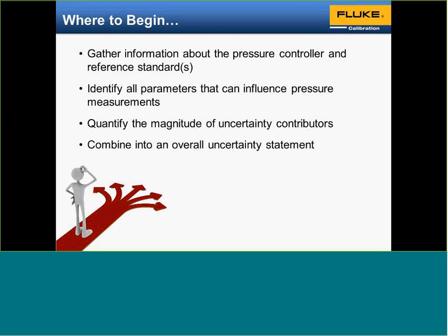All right, let's begin. I find these four steps a good starting point for an uncertainty budget for your pressure controller. Gather information about your pressure controller, the reference standards that were used to calibrate it, and any parameters in your laboratory or the environment that will influence your pressure measurements. You need the magnitude of all the uncertainty contributors, and you combine all of them into an overall uncertainty statement and confidence interval.